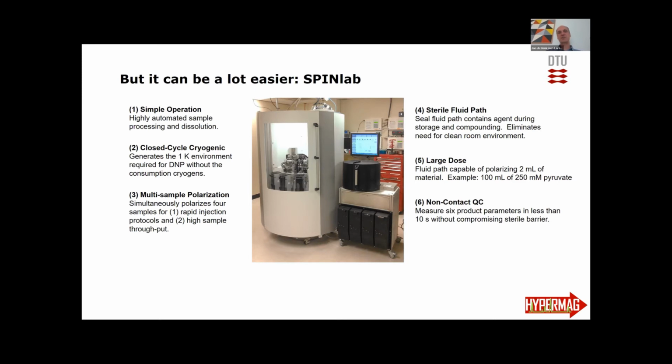In this case, it has 4 independent channels, and we need to ensure that what we inject into the patient is sterile and safe to inject, and that is done by the fluid path, which is a sterile cassette, where we can load the contrast agent in a pharmacy, in a clean room, where we can ensure the sterility of the product.